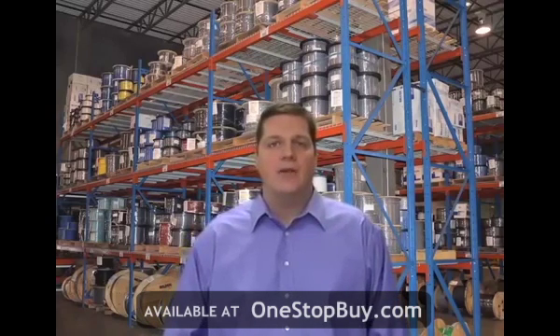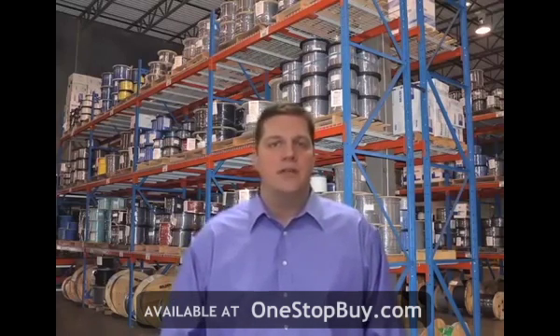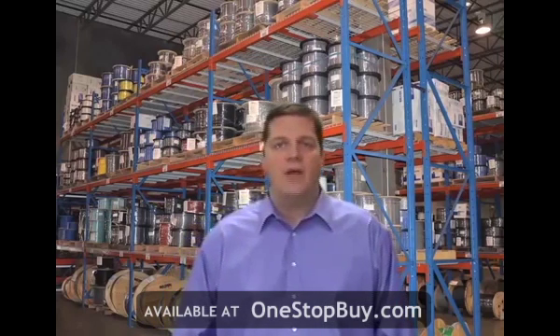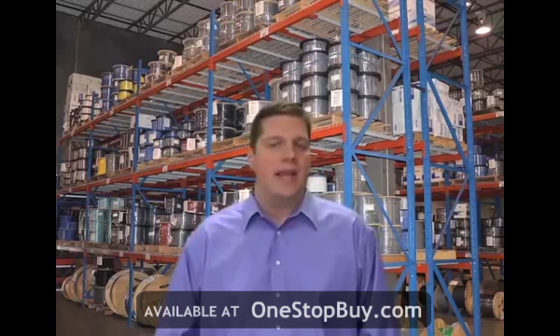Type-G cables are available in three and four conductor constructions from 500 MCM to 8 gauge. These cables are called Type-G because they have a ground wire for each power size wire in the cable.